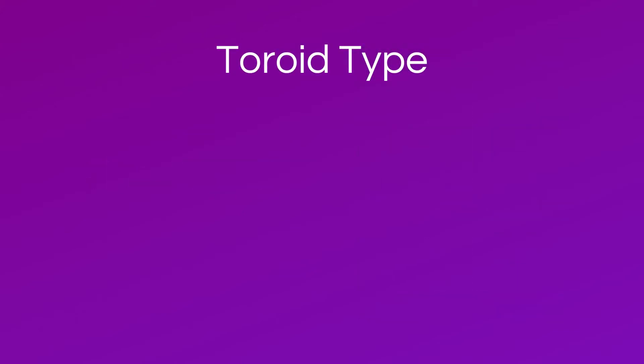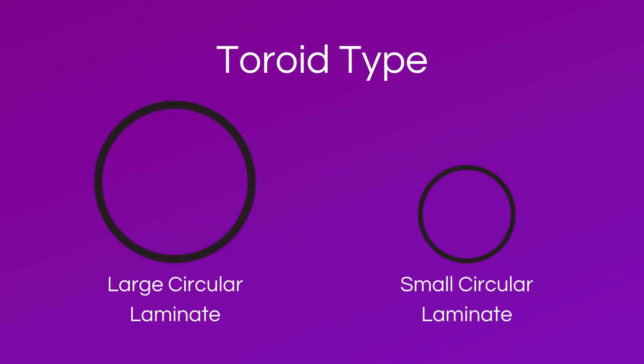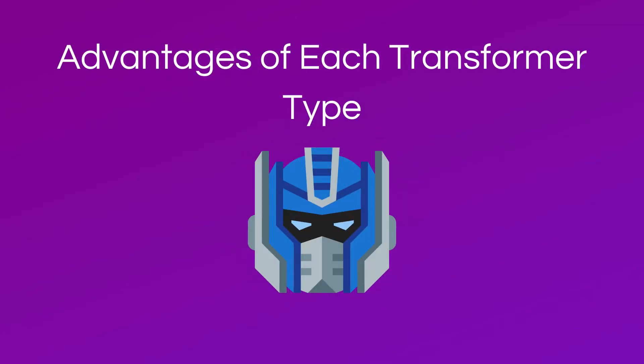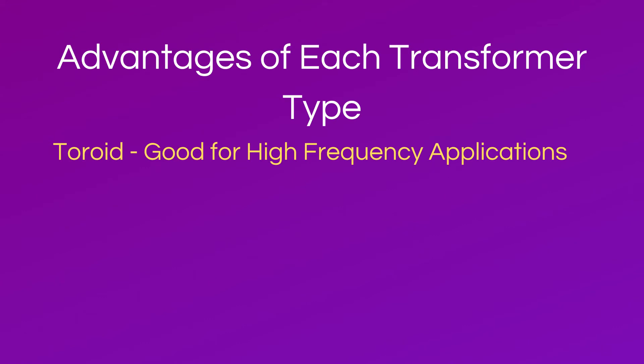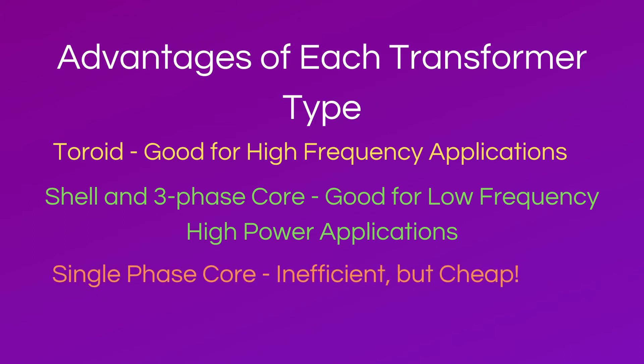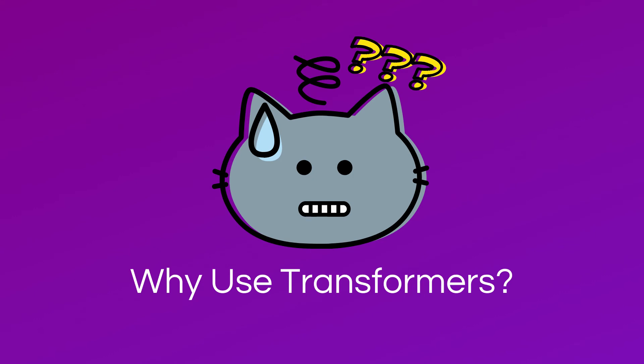The last type of transformer core is the toroid type. It is donut-shaped and uses circular laminates to reduce eddy currents. After the polymer is brushed onto the transformer core, the primary coil is wrapped around it, then an insulator is wrapped around the primary, and the secondary coil is wrapped around that. Toroid transformers are ideal for high frequency applications. Shell type and three phase core transformers are ideal for low frequency, high power applications such as power distribution. Single phase core types, while inefficient due to how far apart the primary and secondary coils are, are the cheapest to make.